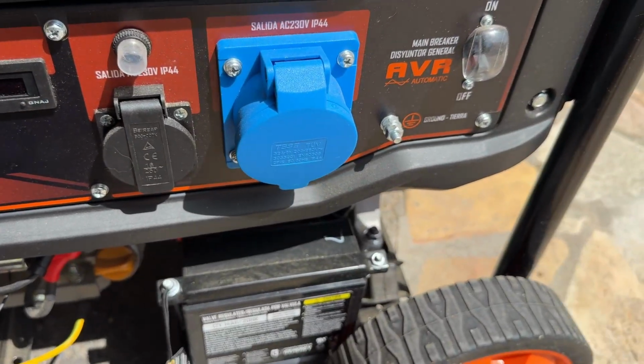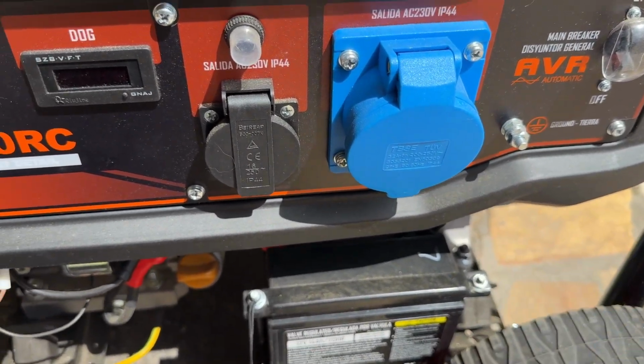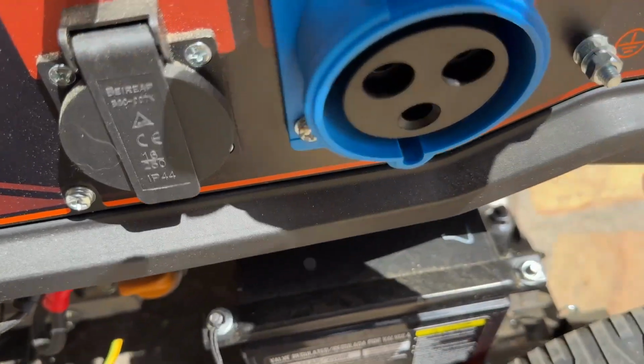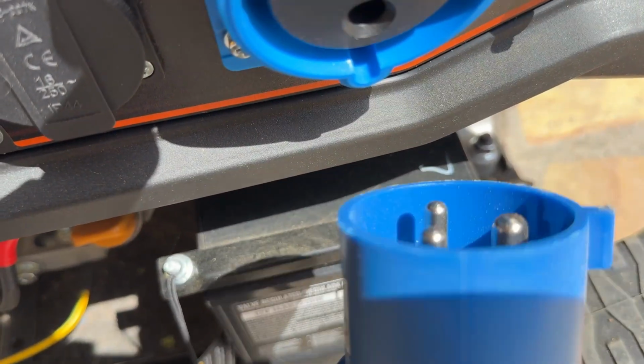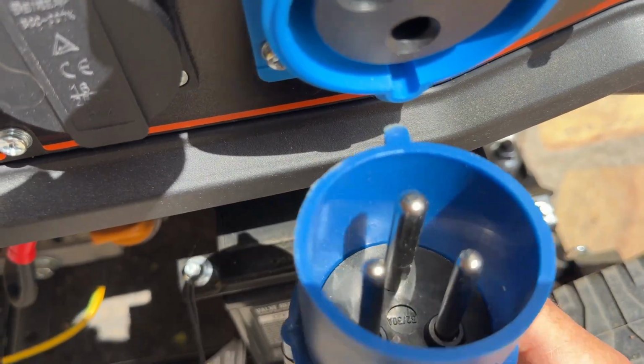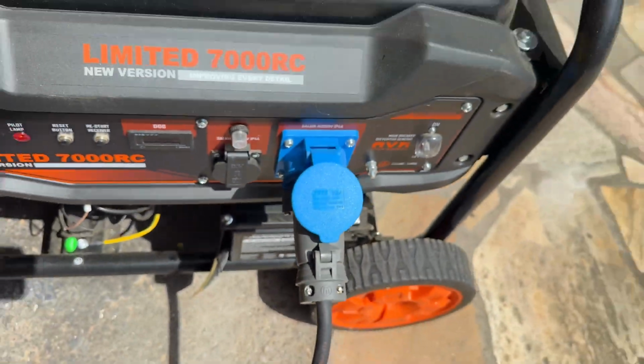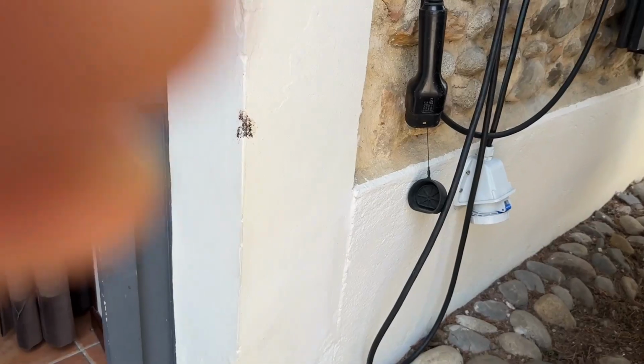I've silenced the audio so I can talk. This is the output socket on the generator, the blue one. The plug from the heavy-duty cable will only go in one way. It's the blue plug. Push that right in. Takes a little bit of force, and make sure the cap goes over the top. The circuit breaker is still open on the generator, so there is no power to this cable right now.